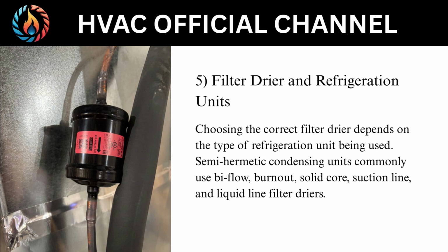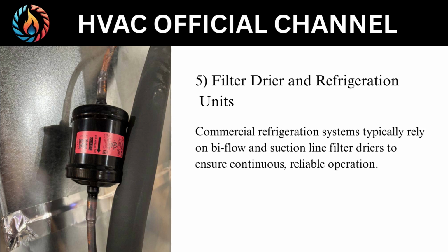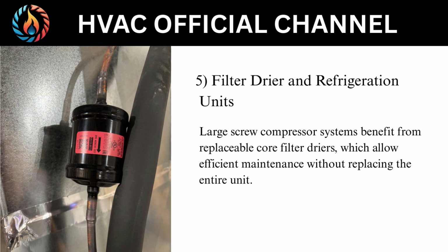Choosing the correct filter dryer depends on the type of refrigeration unit being used. Semi-hermetic condensing units commonly use biflow, burnout, solid core, suction line, and liquid line filter dryers. Commercial refrigeration systems typically rely on biflow and suction line filter dryers to ensure continuous, reliable operation. Large screw compressor systems benefit from replaceable core filter dryers, which allow efficient maintenance without replacing the entire unit.